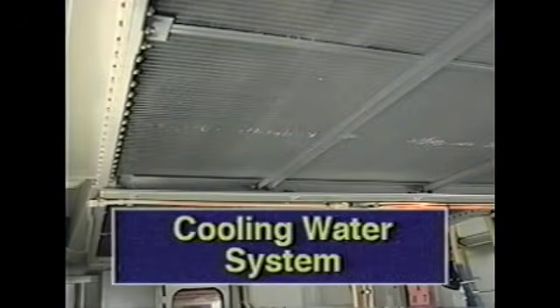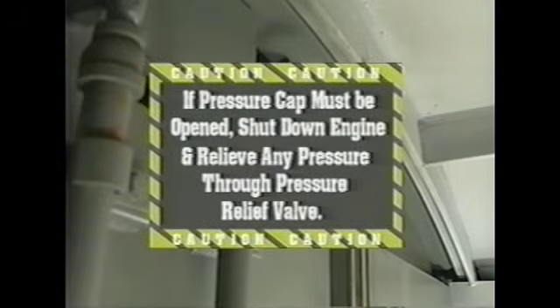The cooling water system has a 210-gallon capacity water tank. Tank level can be determined by the water level sight glass. The tank can be filled through the radiator fill fitting when the radiator fill valve is in the open position. You must relieve pressure in the cooling system before adding water by opening the pressure relief valve. Caution: if the pressure cap must be opened, shut down the engine and relieve any pressure through the pressure relief valve.